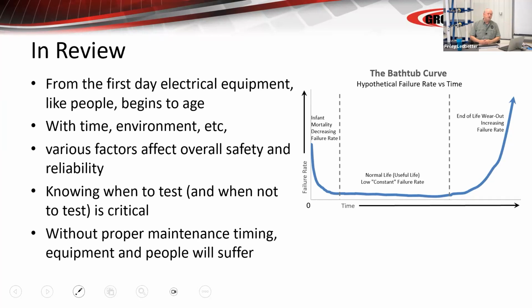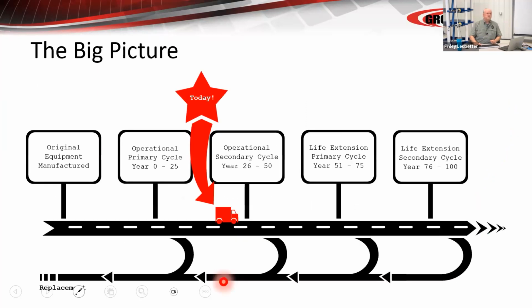If it's a critical circuit, you've got to consider changing and not sticking with the old way of doing maintenance as far as the timing goes, or even the tests and the cleaning and the inspections that you're doing. They may need to change as the equipment ages and as your loads increase. Okay, let's see if we can change the next slide.